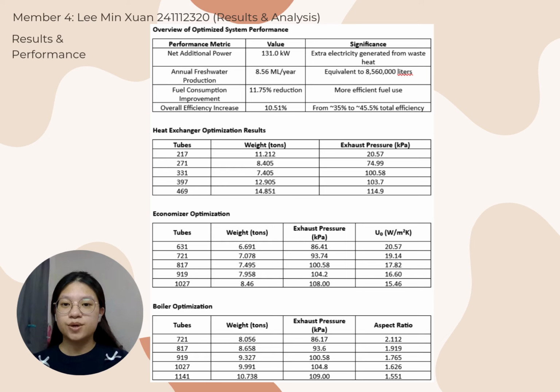For the economizer, which preheats incoming seawater, we select 817 tubes. This design weighs 7.495 tons, has an aspect ratio of 1.677, which is very compact, achieves a heat transfer coefficient of 17.82. Most importantly, it maintains exhaust pressure above 100 kilopascal. The boiler, where seawater turns to steam, uses 919 tubes, weighs 9.327 tons, with a heat transfer coefficient of 19.46. These were chosen over lighter options because the 721 and the 817 tube designs couldn't meet the 100 kilopascal pressure constraint.